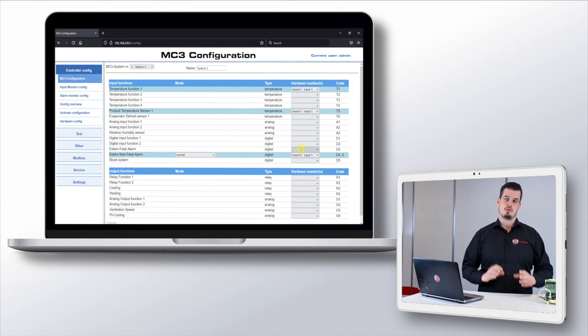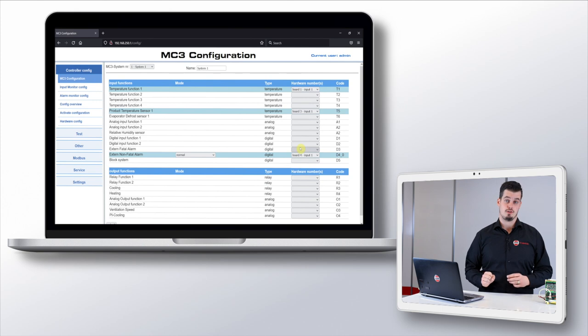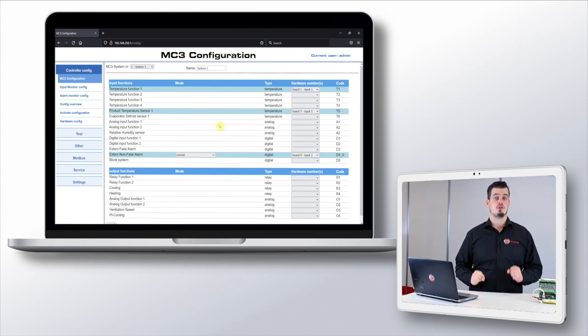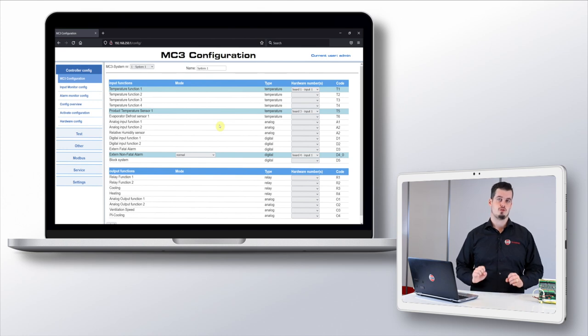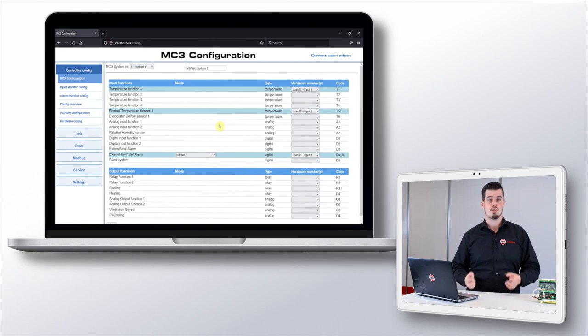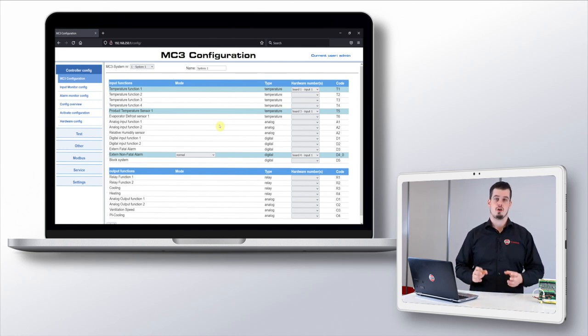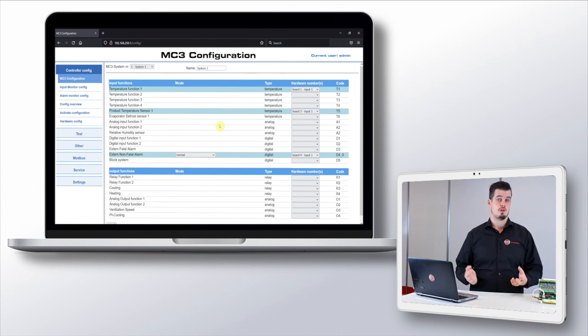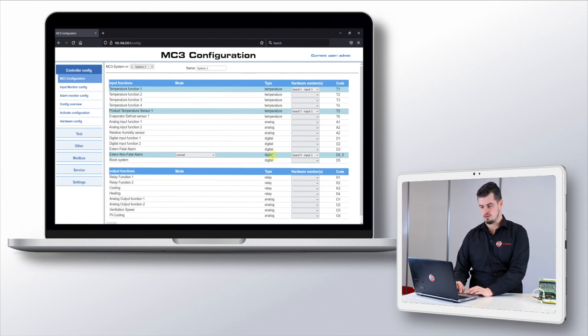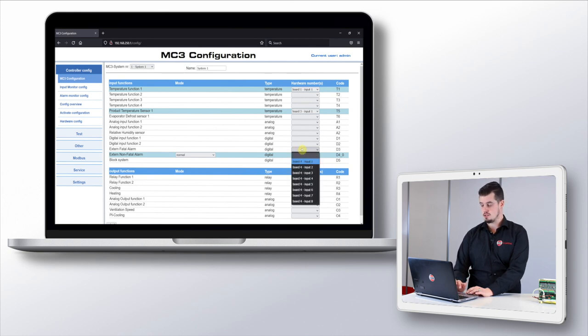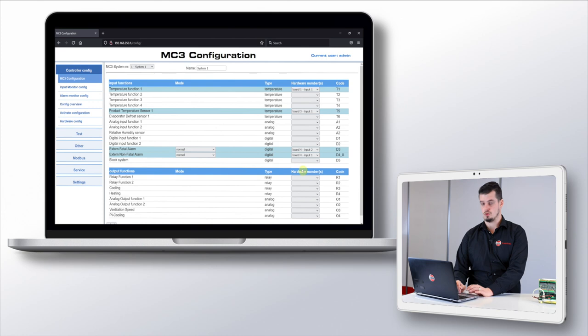For our second example we'll take an alarm signal connected to a digital input on board 4 input 2. We want this signal to trigger an alarm if the signal is low or disconnected. So how do we do this? We go to our function, external fatal alarm, press on the dropdown and select board 4 input 2.